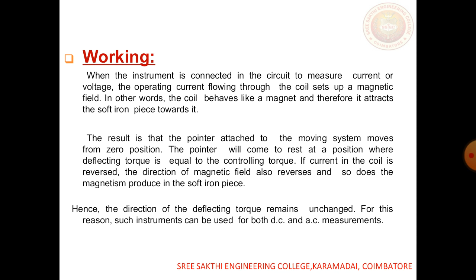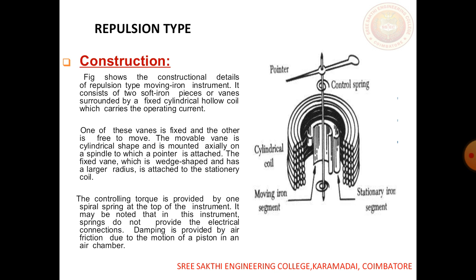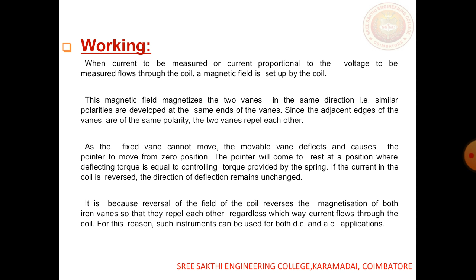Next, repulsion type. Repulsion type is again a moving iron instrument. It consists of two iron pieces, vanes, surrounded by a cylindrical hollow coil which carries the operating current. Here, one of these vanes is fixed and the other is free to move. The movable vane will be a cylindrical type which is kept at the axial axis. The controlling torque is provided using the spring. This spring will hold the pointer at that point. So this is called repulsion type of instruments. The working procedure, everything is given here.